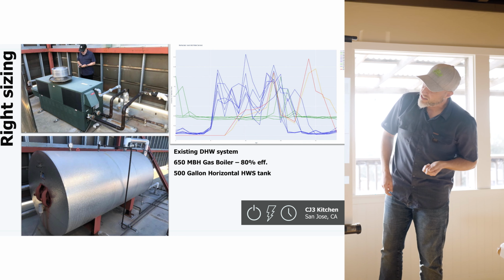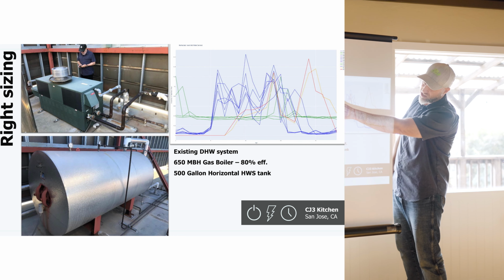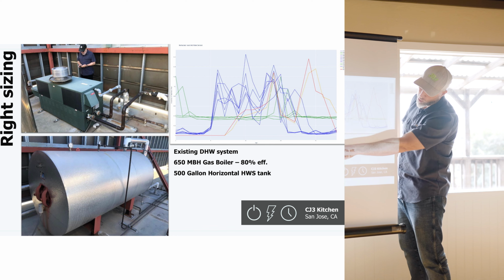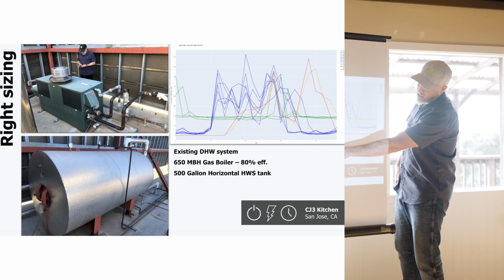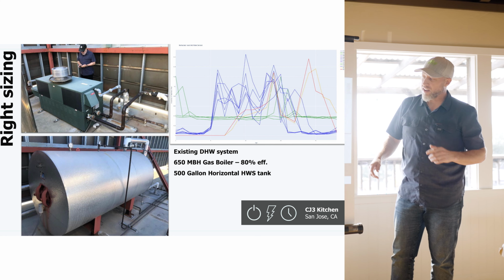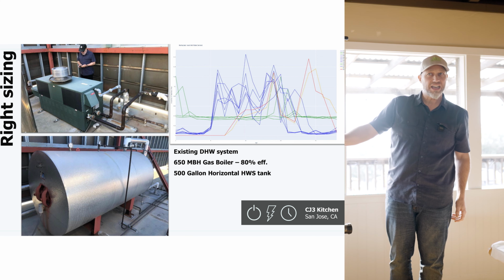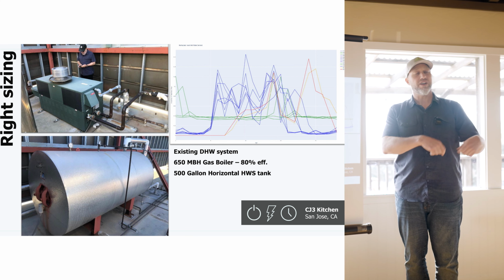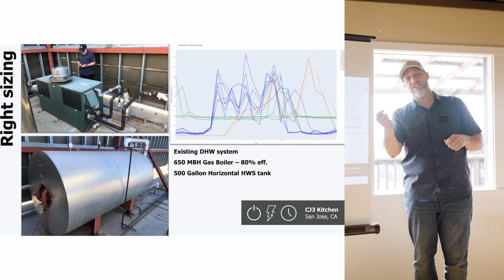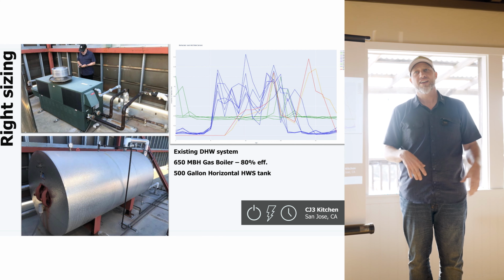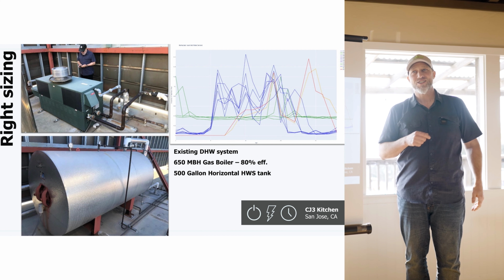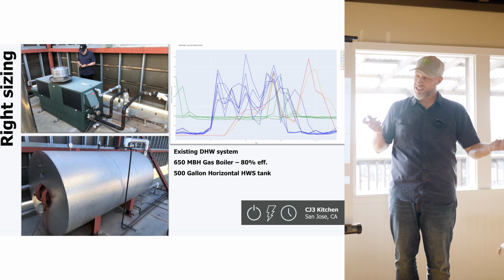Here's what it looked like: a 650 MBH boiler with 500 gallons of storage. The contractor initially did a like-for-like on this 650 and said he wanted a heat pump water heater, then went to a contractor who gave him a $1 million bid. The client said no, get out of here. So they came to us and asked for help, and we said, yeah, let's meter the building.